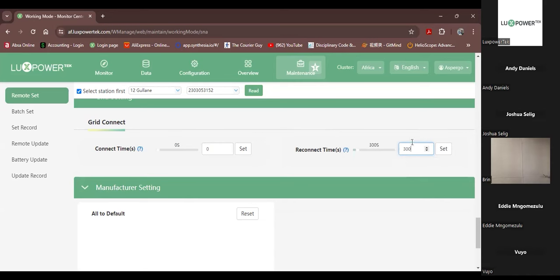This simply means that when the grid comes on, the inverter will count down this timer. And only when the timer gets to zero will it connect, will it close the grid relay. Even though load shedding has finished, at 300 seconds the inverter will wait 5 minutes before it reconnects the grid to the inverter. This is a prerequisite now for the City of Cape Town, and I'm sure many of the other municipalities will follow suit. So you guys will be very happy to know that this function is now available.